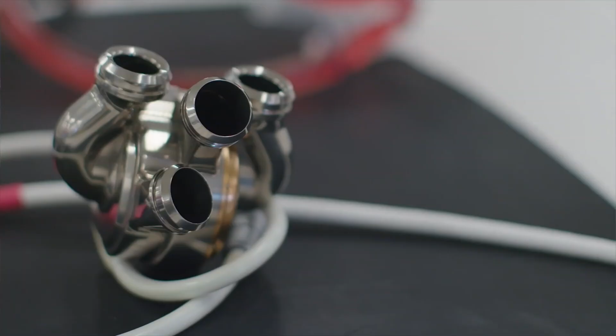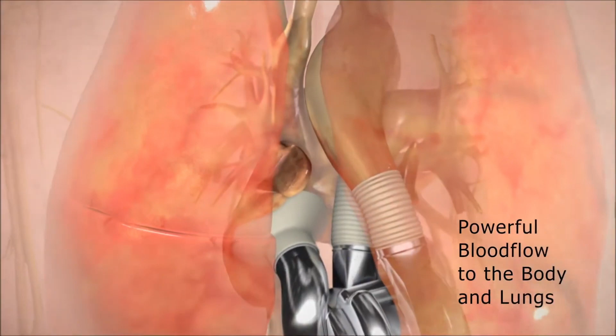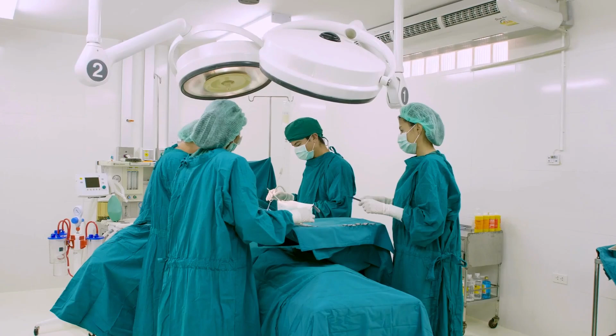But the durability of the Bivacor TAH goes beyond just its materials. Remember that single moving part that we mentioned earlier? That's a key factor in the device's potential longevity. There are no valves, no flexing ventricle chambers or pumping diaphragms, and no mechanical bearings. The non-contact suspension of the pump rotor via magnetic levitation eliminates mechanical wear within the pump. This design approach could potentially allow the Bivacor TAH to function for much longer periods than traditional artificial hearts, providing a more reliable bridge to transplant for patients.